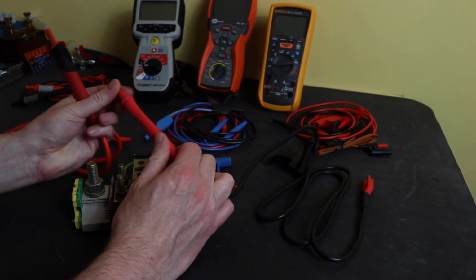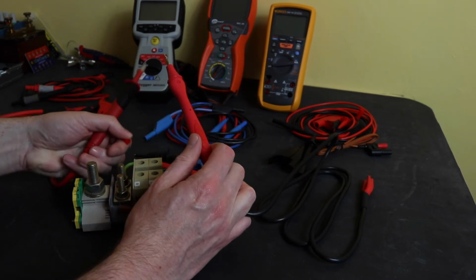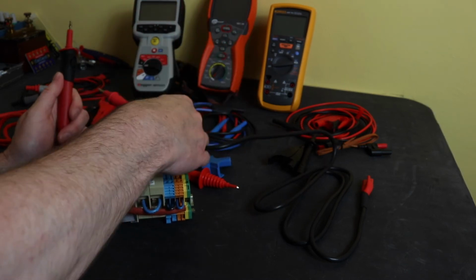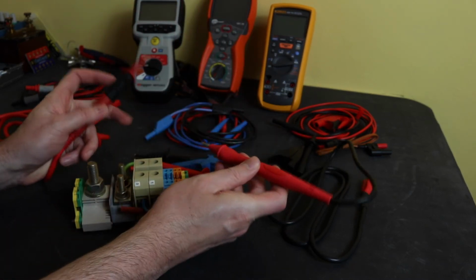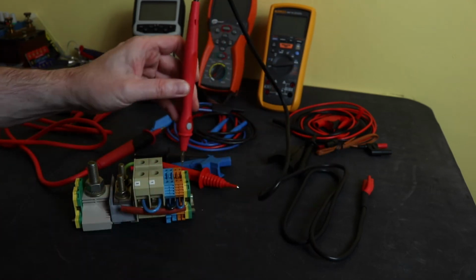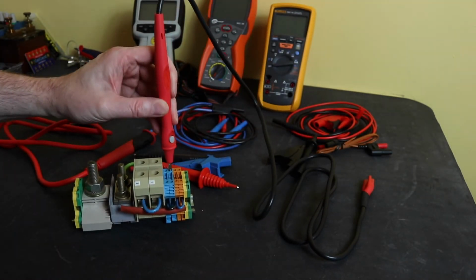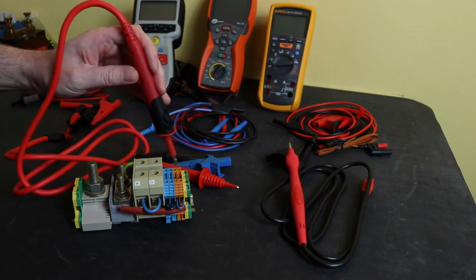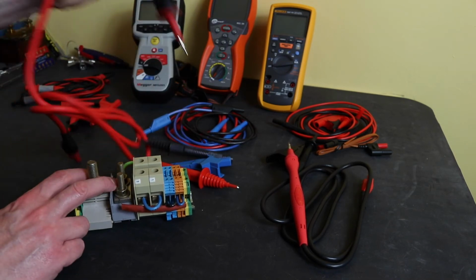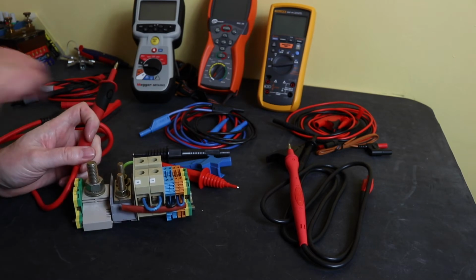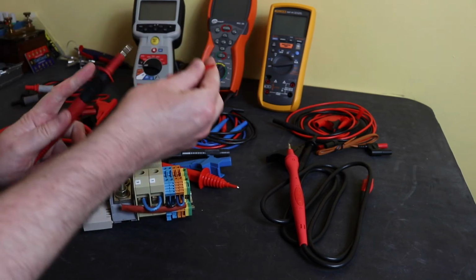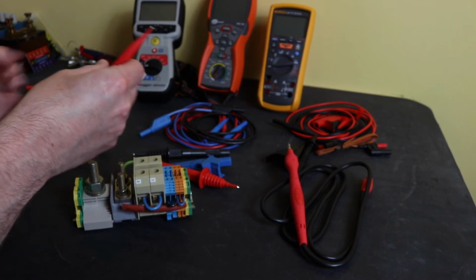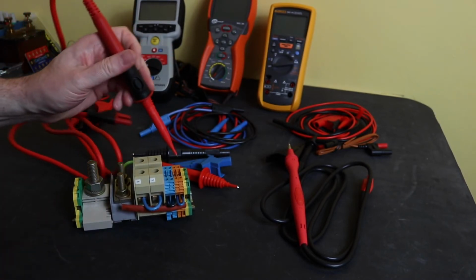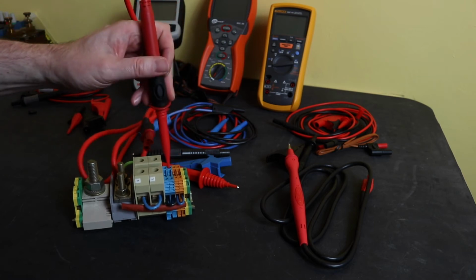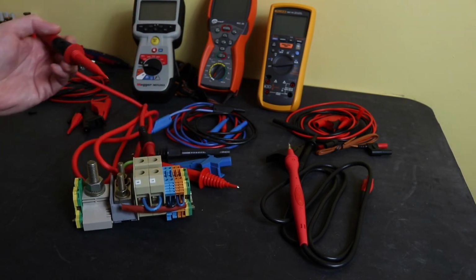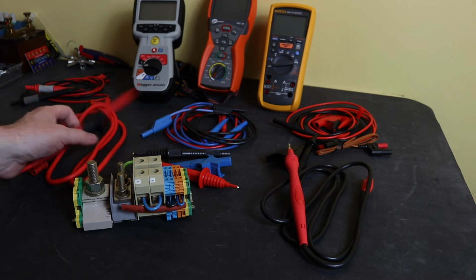Both of them have a removable GS38 cap, which if you want to get into the smaller terminals you'll need to remove, and then you can get into any of the terminals you require, really. It's tighter on the Megger. What the Megger does have is an extension probe that you can put on, and then you can maintain the GS38 protection. You can get in all terminals you like there. So that's quite a nice feature.